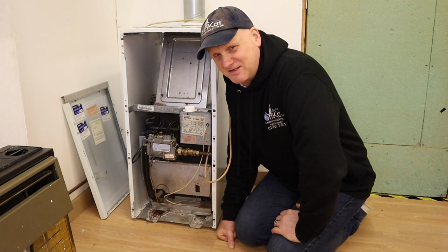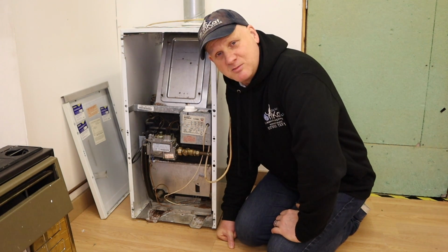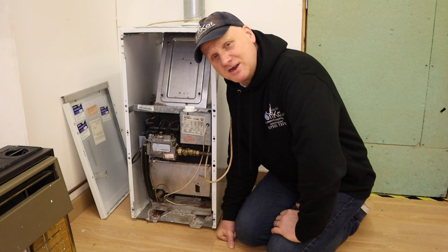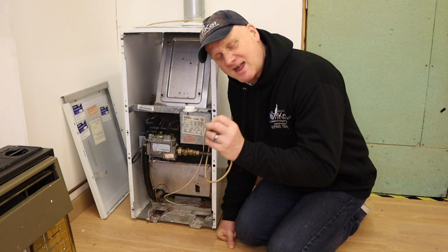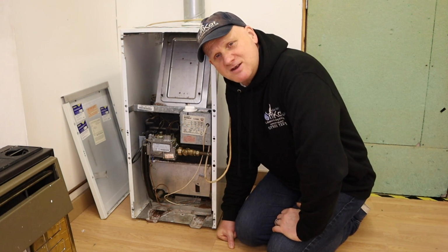Well, I'm saying manufacturers don't use cast iron heat exchangers, but you may still find some out there on condensing boilers where they use a secondary heat exchanger made of stainless steel.